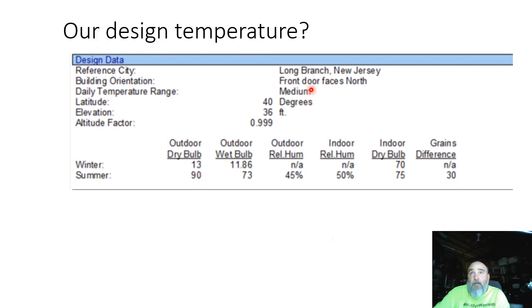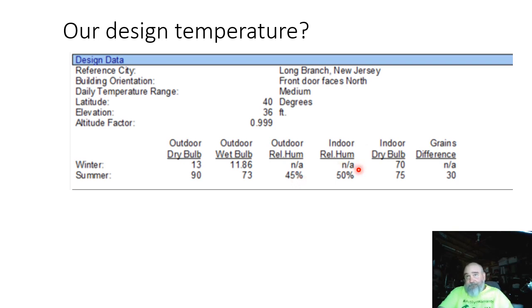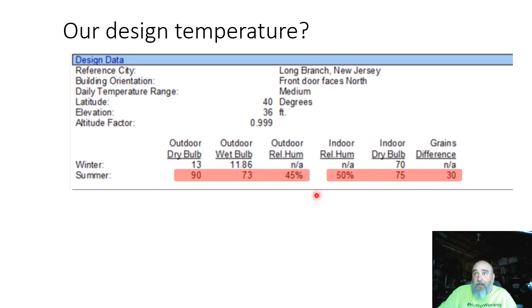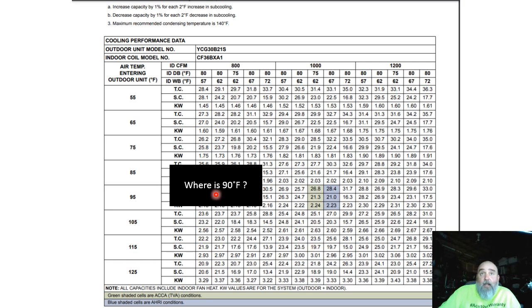Our design temperature — I used Long Branch, New Jersey because it's close to the host of the class I'm doing on Monday. 90°F is our summertime outdoor temperature, wet bulb 73°F. Outdoor humidity at 90°F is 45%. We're a green-grass climate: 75°F inside, 30 grains difference.